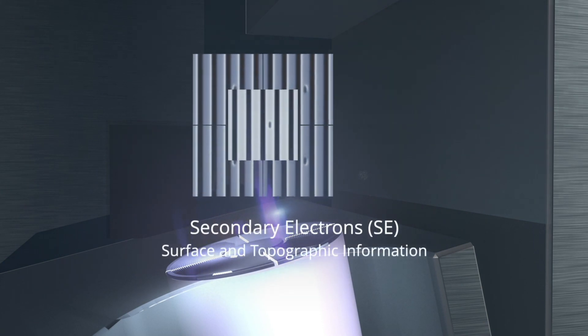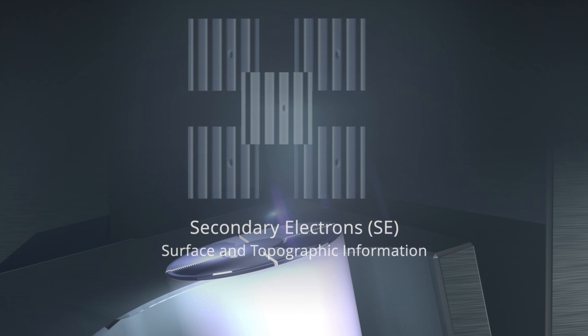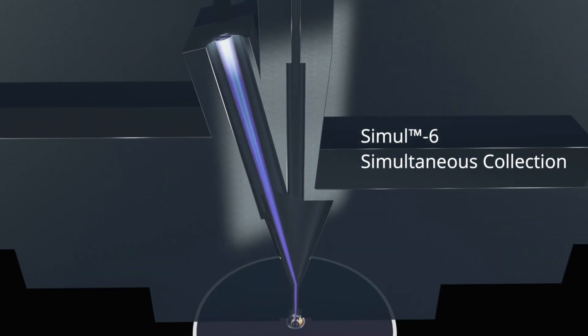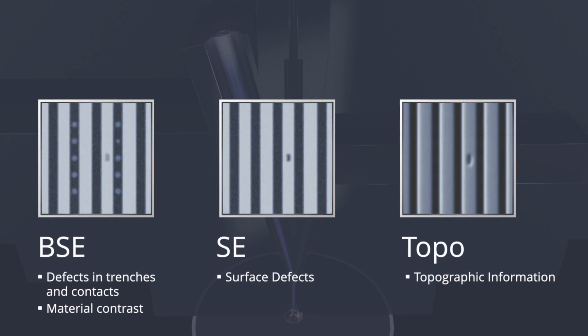Six channels work simultaneously to collect various signal types from defects. The signal collected from secondary electrons provide surface and topographic information. The backscattered electrons provide information on material contrast and defects in deep structures.